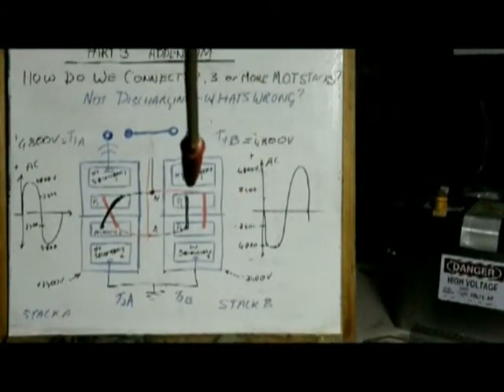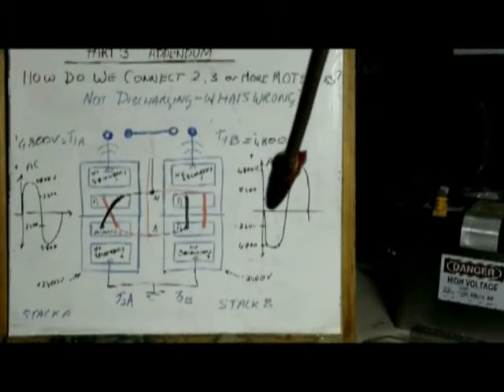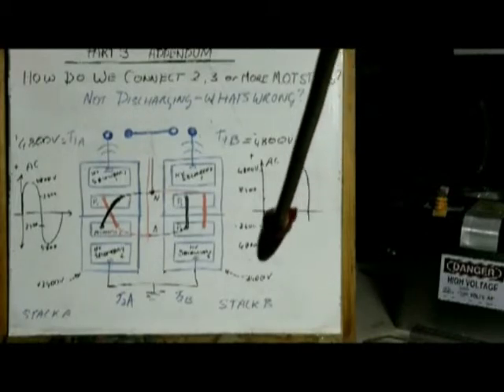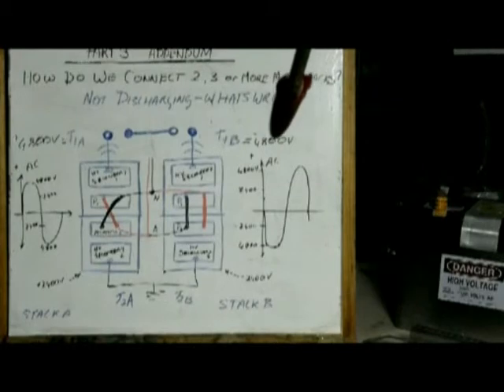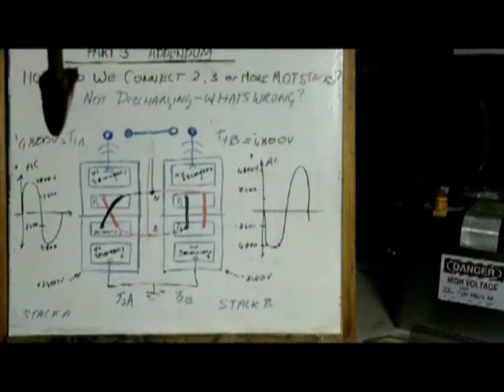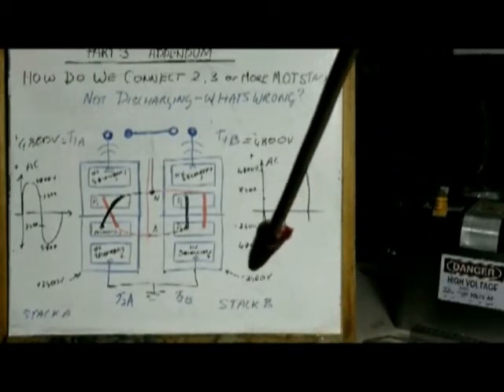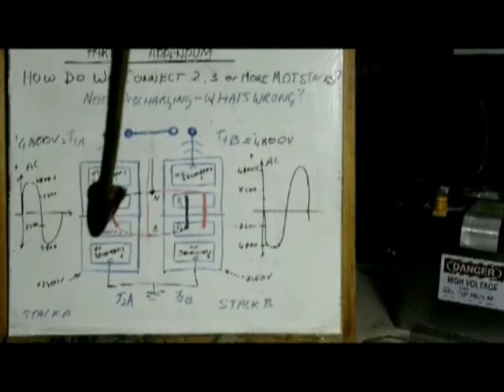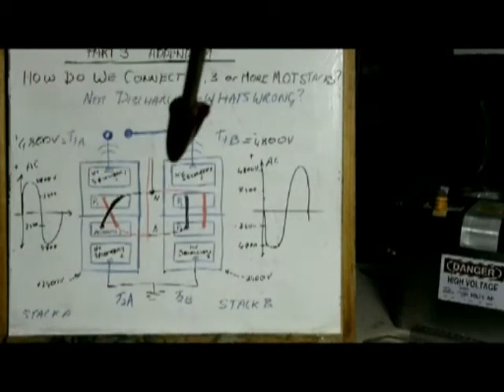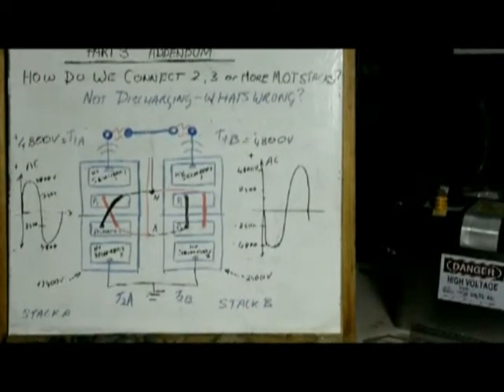Okay, as if by magic, these connections have now reversed. As you can see, the black wire is now connected to the active on this one, and the red wire is now connected to the neutral on this one. Okay, and what's happened suddenly? Wow, it's out of phase, 180 degrees. So when this one is minus 4,800 volts, this one is plus 4,800 volts. This also suddenly changes things a bit. This core is now minus 2,400, and this core is 2,400 plus at that particular moment in time. And voila, we have discharges.